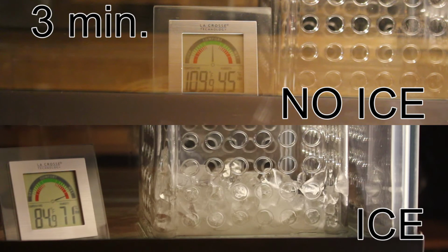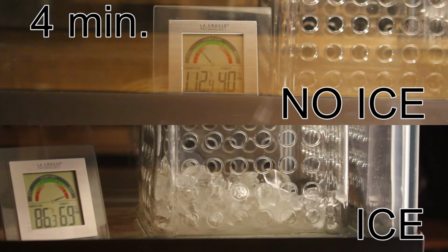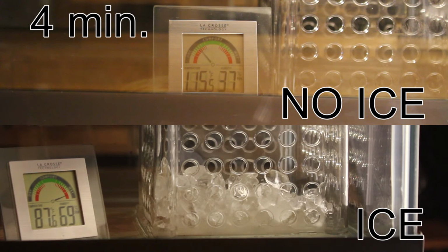It's not the greatest source of cooling because you have to physically lug a block of ice to your data center in order to cool it down, like in olden days. Ice melting is not the quickest endothermic process in the world. It's a phase change from solid H2O to liquid H2O. In general, a more practical phase change is to take some liquid and convert it into a gas. This can be water evaporating over a coil, or it can be high pressure refrigerant recirculating from liquid to gas and back again in a closed loop. But either way, you're looking at the same type of energy change as it took to melt this ice, which is why we can express it in tons.